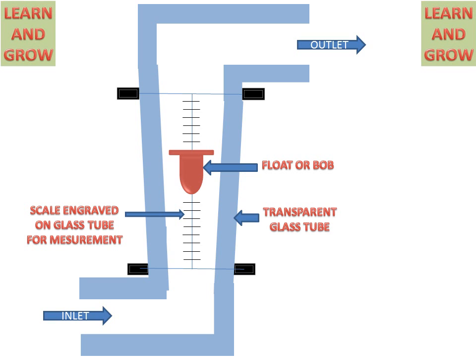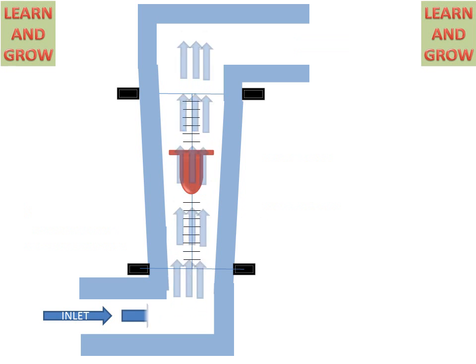When flow is very high, it will push the bob in the upward direction. When the gravity pull balances this push, the float will be in equilibrium and stop. We can then get the reading from the scale and flow will go outside. This is high velocity measurement.